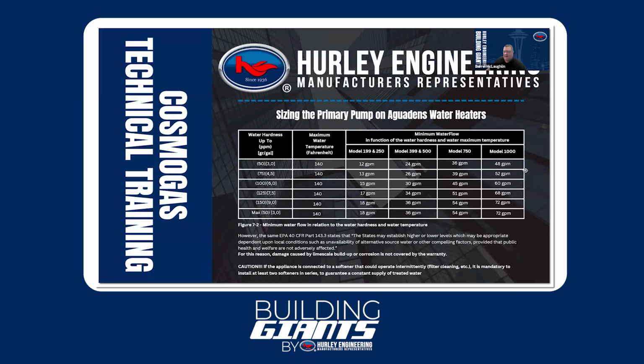Let me go back here. So, and that will change. If I'm doing 1,000,000 BTUs, then I would be 60 gallons per minute. Or if my hardness changed, I would just have to find the corresponding spot on this graph and then select my minimum flow rate for that F1 flow circuit.